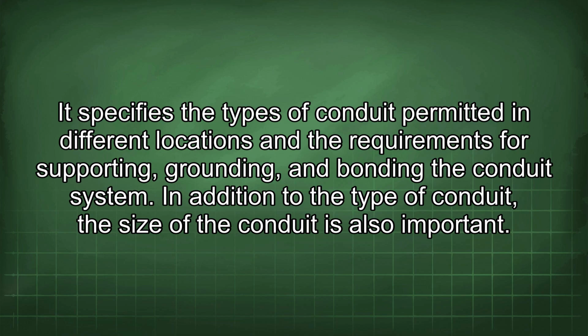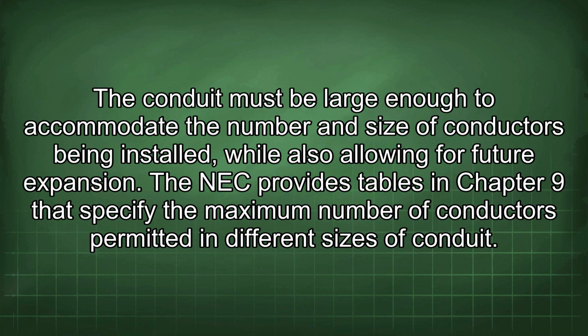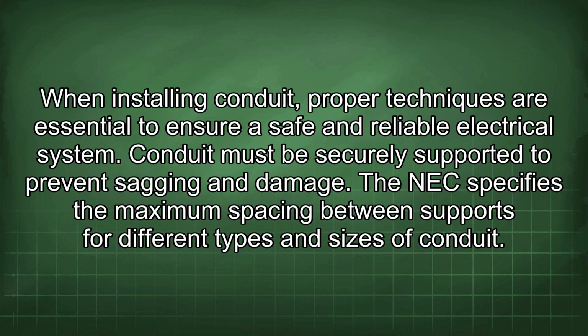In addition to the type of conduit, the size of the conduit is also important. The conduit must be large enough to accommodate the number and size of conductors being installed, while also allowing for future expansion. The NEC provides tables in Chapter 9 that specify the maximum number of conductors permitted in different sizes of conduit. When installing conduit, proper techniques are essential to ensure a safe and reliable electrical system.